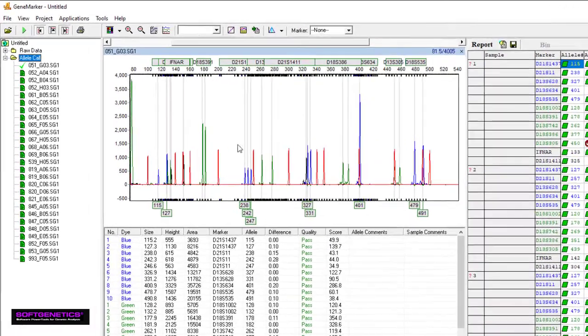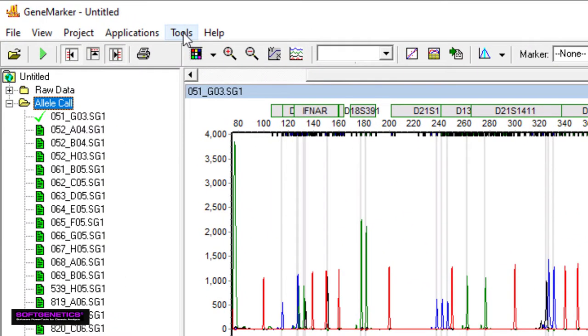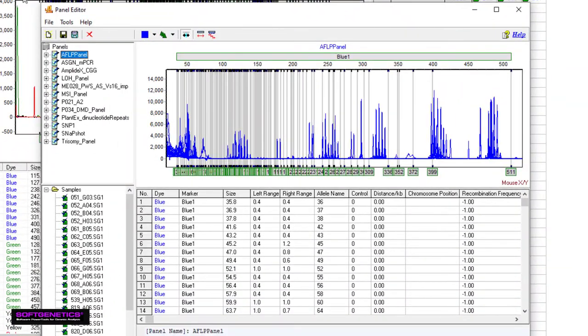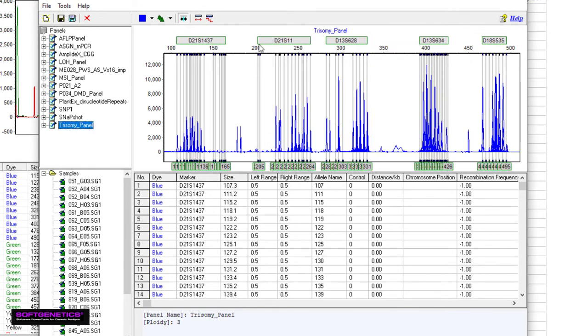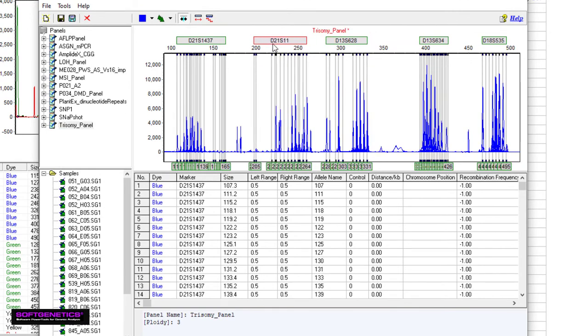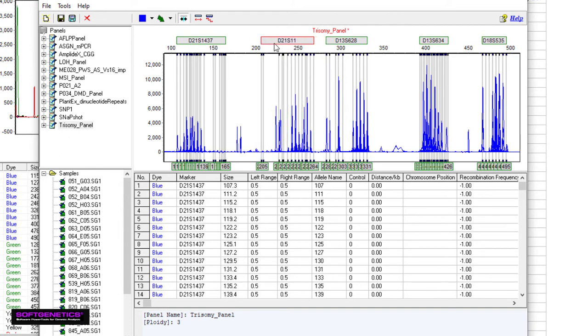One last feature I'd like to show you is the Panel Editor. The Panel Editor can be accessed through Tools, Panel Editor. As expected, here you can organize and modify your panels. A particularly useful feature of the Panel Editor is that entire markers can be shifted by holding the Shift key and dragging the mouse. This ability lets users easily correct misalignment due to samples running more quickly or slowly than expected on the CE apparatus. We go into a little more detail on Panel Calibration during its own webinar.